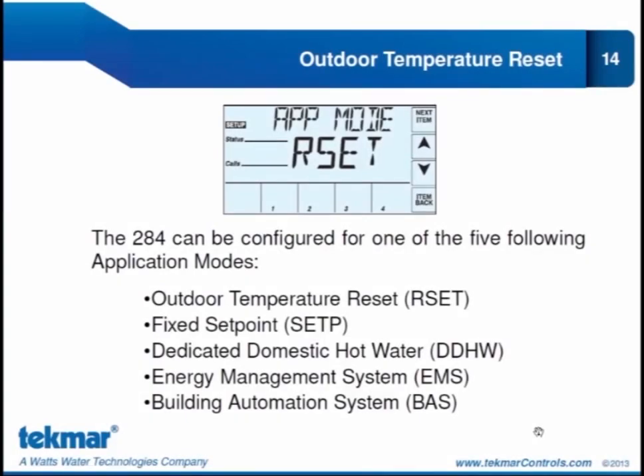The 284 can be configured for one of the 5 application modes. We have the outdoor temperature reset mode, and 4 of the 5 applications that we reviewed in this webinar were the outdoor temperature reset mode. If that's not what we're looking for, we can set up the 284 for a fixed set point mode, for dedicated domestic hot water mode, which was one of the other applications that we saw. We can also configure it to receive input from an energy management system or from a building automation system.